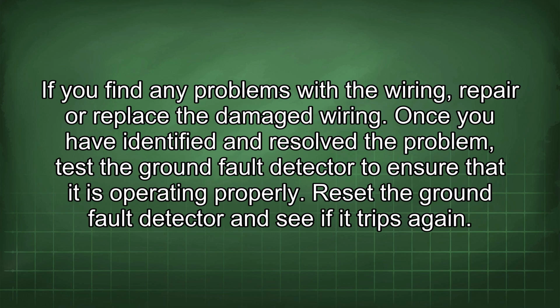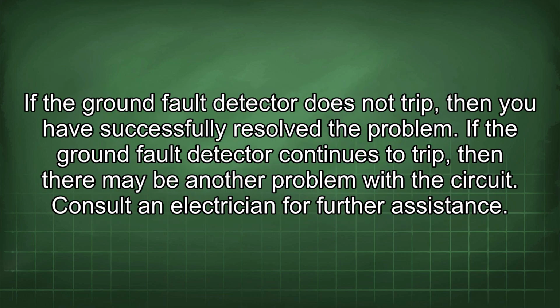Once you have identified and resolved the problem, test the ground fault detector to ensure that it is operating properly. Reset the ground fault detector and see if it trips again. If the ground fault detector does not trip, then you have successfully resolved the problem. If the ground fault detector continues to trip, then there may be another problem with the circuit. Consult an electrician for further assistance.